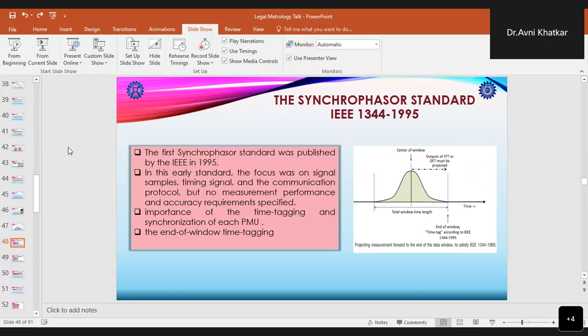However, this early standard only provided details about the signal samples, timing signal and the communication protocol, but no measurement performance and accuracy requirements were specified. Also in this standard, there was a discussion of the importance of time tagging and synchronization of each PMU and its sampling process to the UTC. However, the time tag assigned to each report was defined as being coincident with the last sample taken in the data processed to create each report, as shown in this figure.